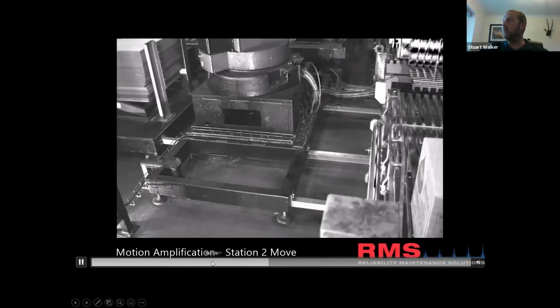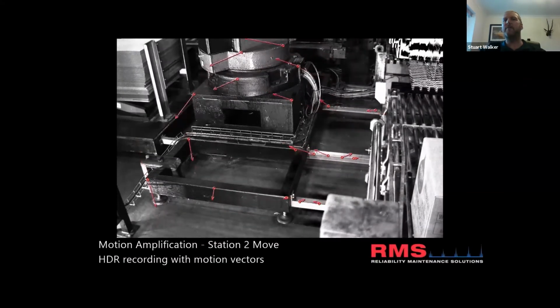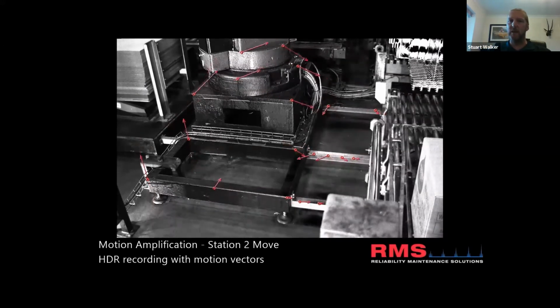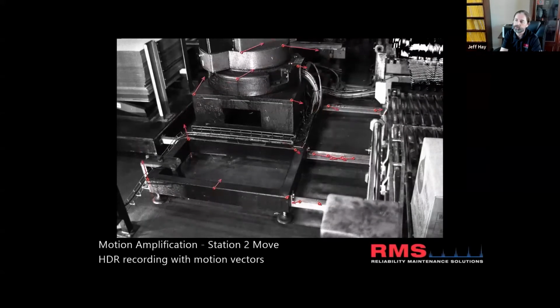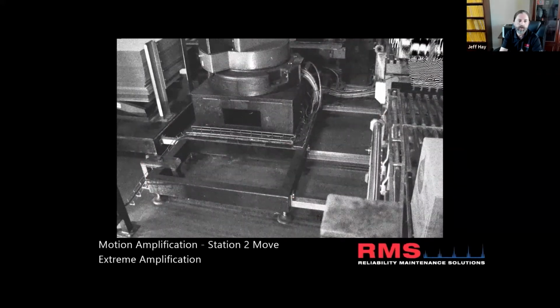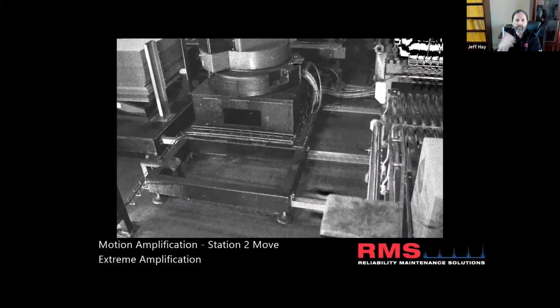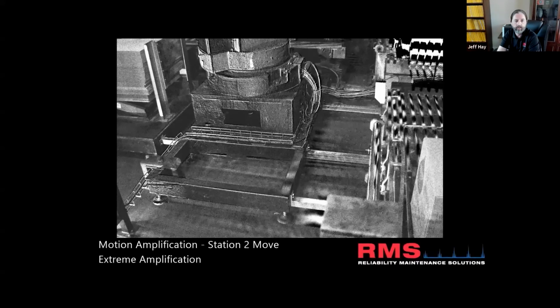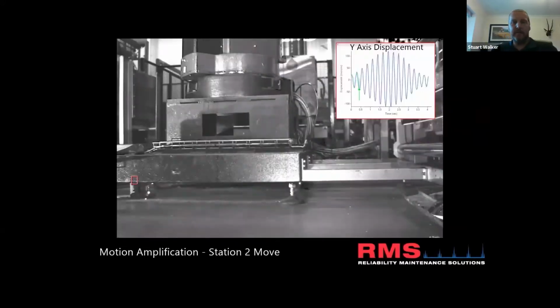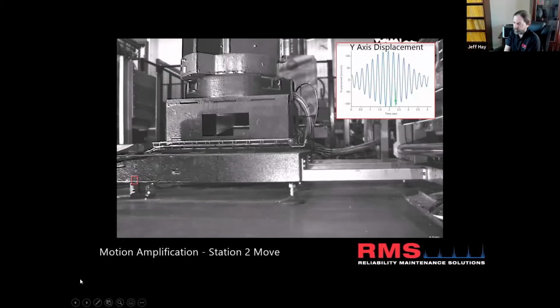Like I said, the whole cycle was 2 minutes, so it's a 2-minute acquisition, where a lot of the time on a pump or rotating kit we're probably doing 3-5 seconds. It's a good point, because we get a lot of people that look at kilns or slow moving stuff. A good takeaway is don't be hesitant to drop your frame rate, because if you don't need to see above 30 hertz, you don't need to collect the data. There's no real reason to do it. Exactly, it makes the data more manageable as well.